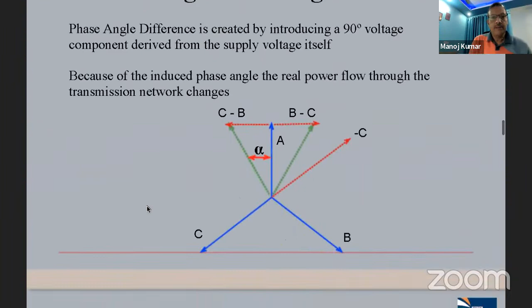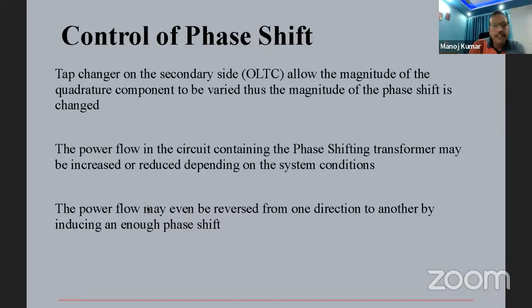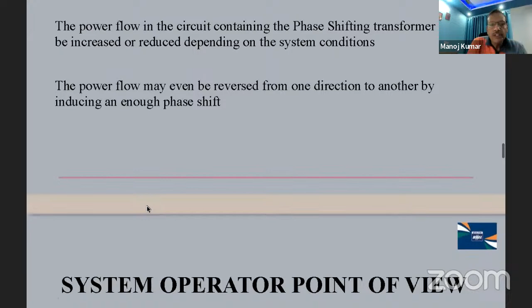To control how much I have to change the power flow, I have to control the phase angle alpha. This alpha I can control by the OLTC. The OLTC is already installed in the transformers. By sitting in the control room itself, I can change the OLTC step value, and by changing it I can control the power flow in the transmission line.